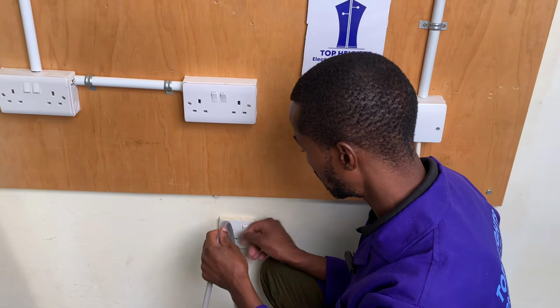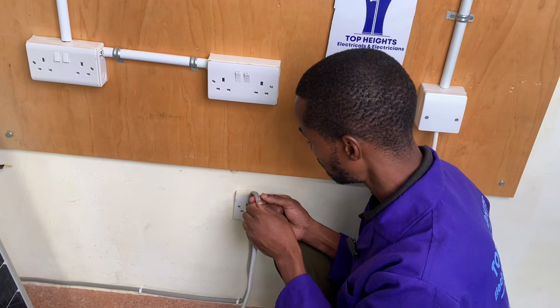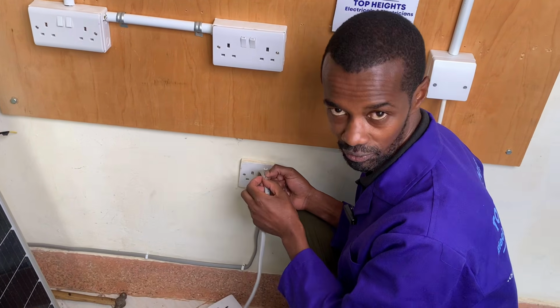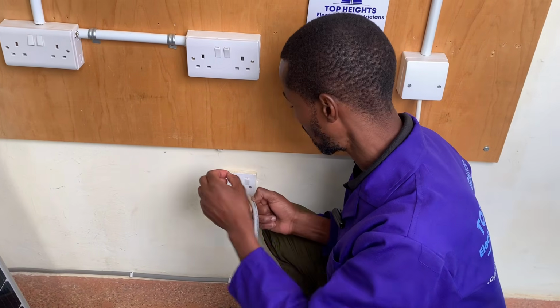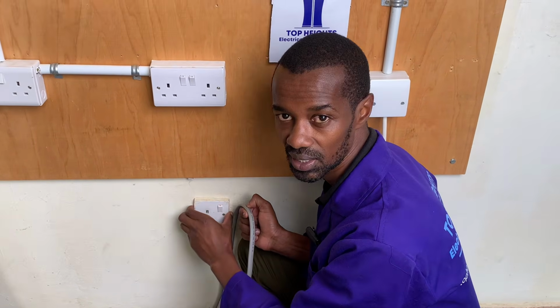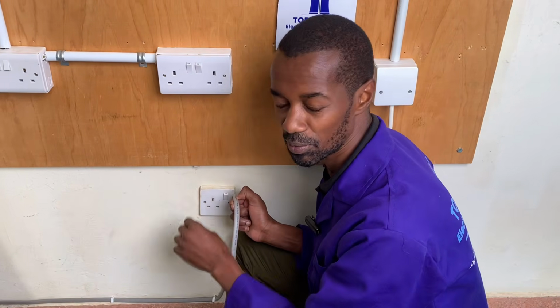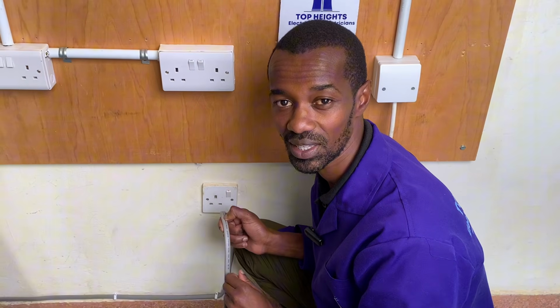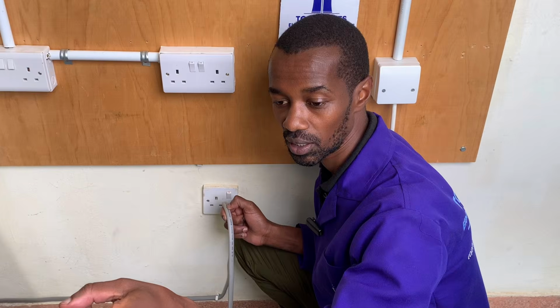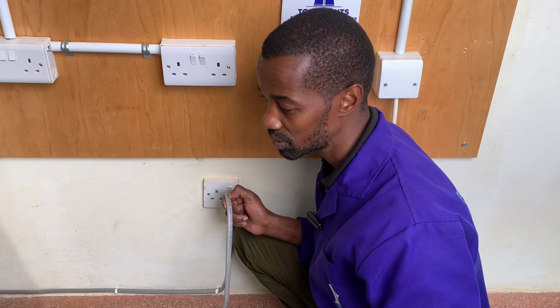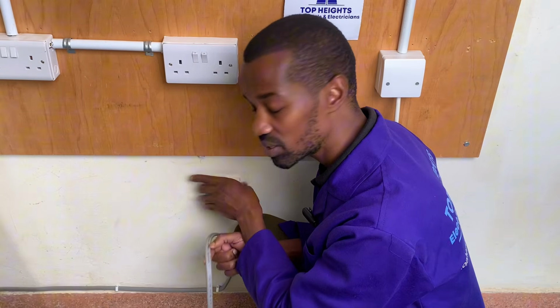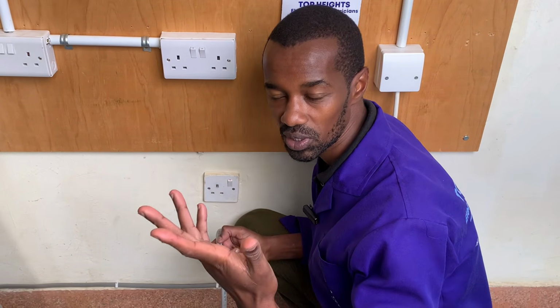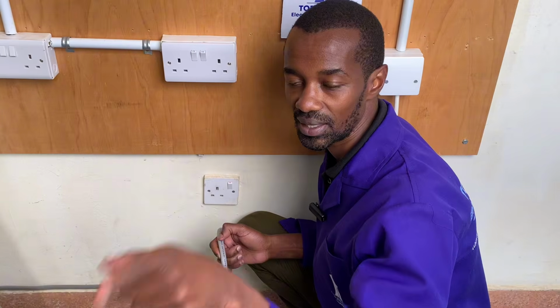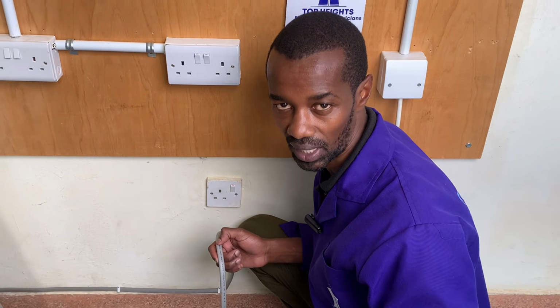Now I will simply cut this cable at this point, remove the insulation, and then terminate it at this point. After we are done with that, before we even turn the MCB back on, we'll terminate at that point, then activate the MCB, test whether this socket is working as it was, and then test the other extension we have done.